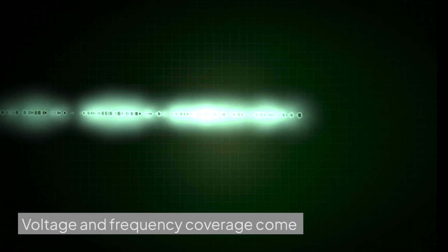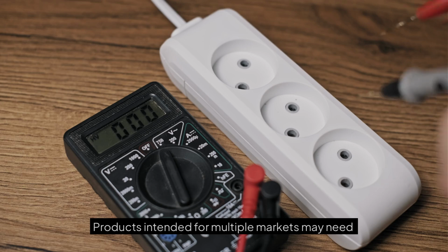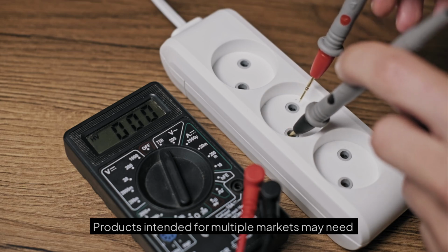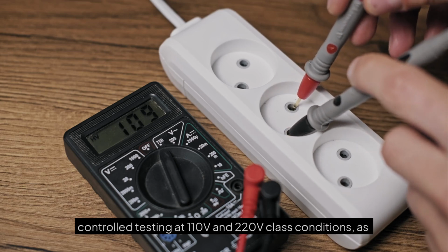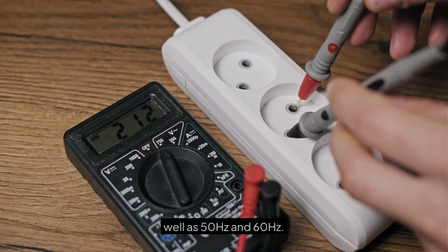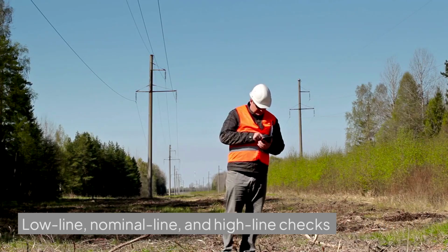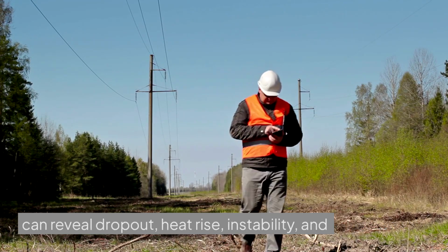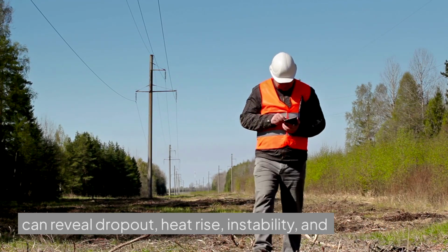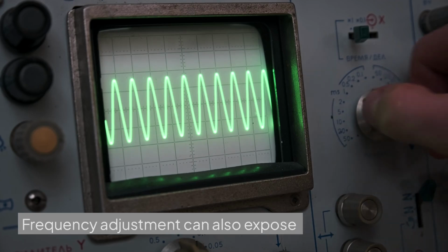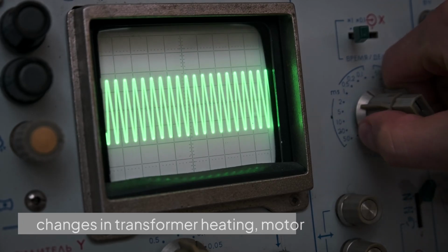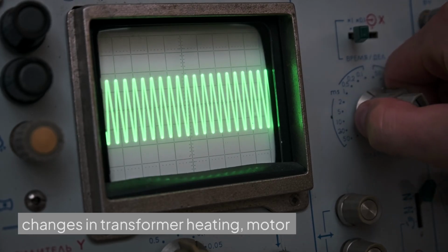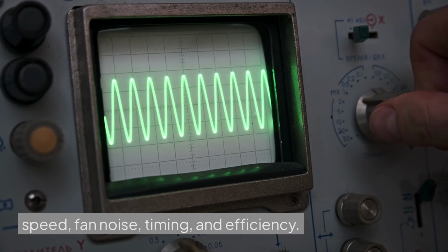Voltage and frequency coverage come next. Products intended for multiple markets may need controlled testing at 110V and 220V class conditions, as well as 50 Hz and 60 Hz. Low line, nominal line, and high line checks can reveal dropout, heat rise, instability, and reduced design margin. Frequency adjustment can also expose changes in transformer heating, motor speed, fan noise, timing, and efficiency.